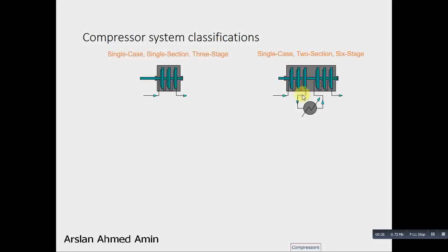So here we see that the gas, we cool the gas. This is the symbol of cooler. So we cool the gas, then it again is being compressed. Again the cooler is installed for achieving volumetric efficiency. Because for the hotter gas, we would need greater volume to accommodate gas at such high temperature.